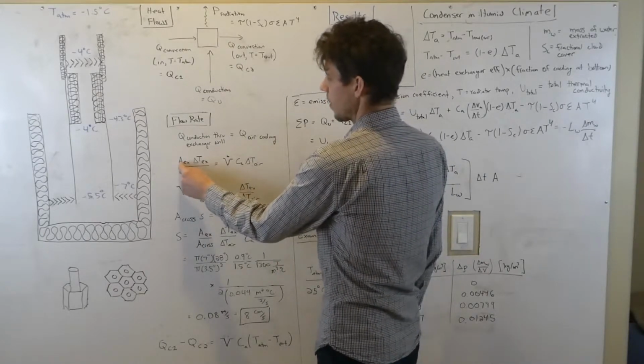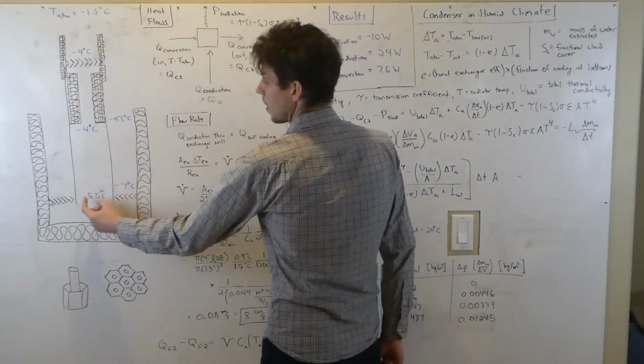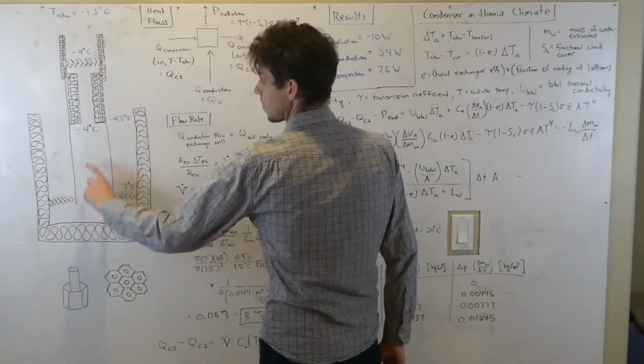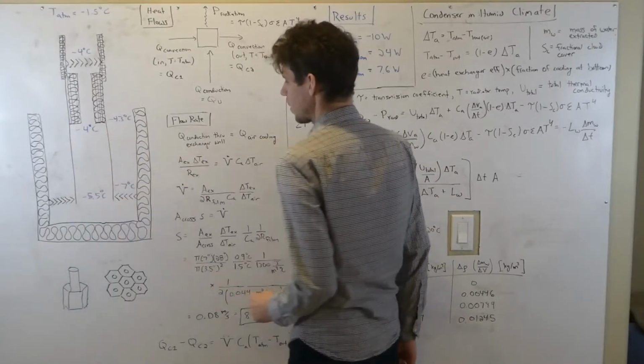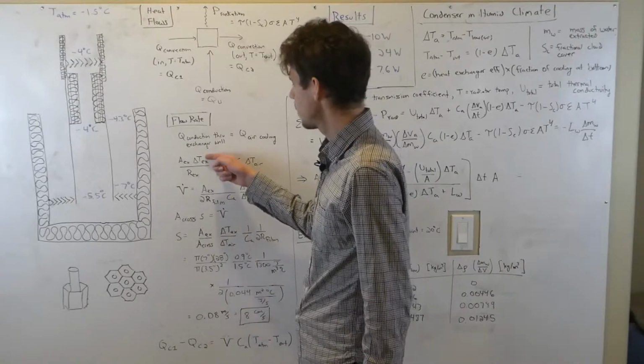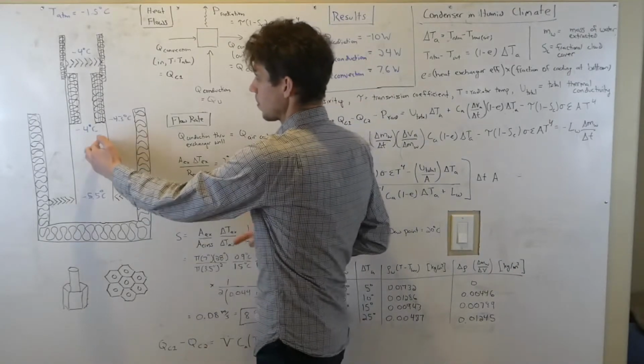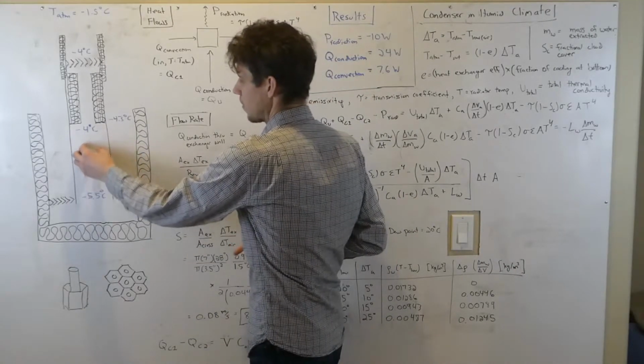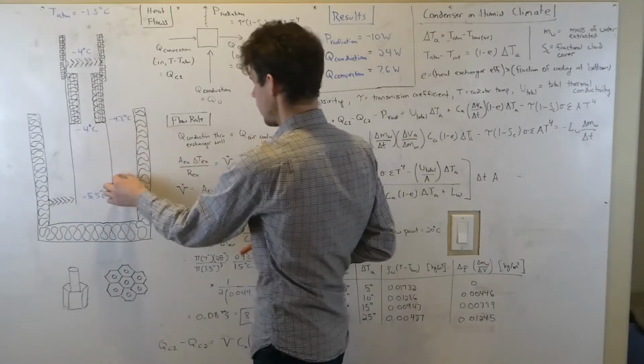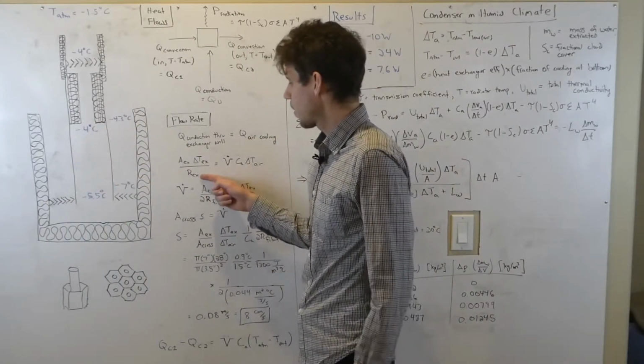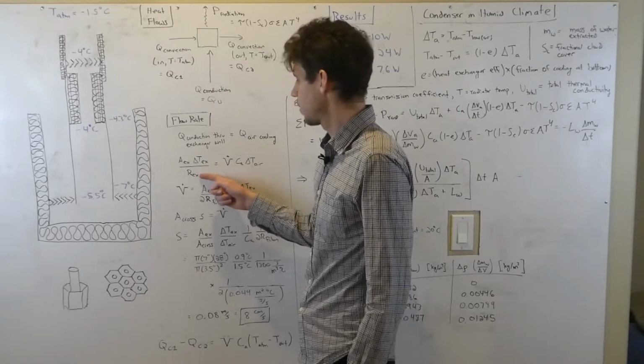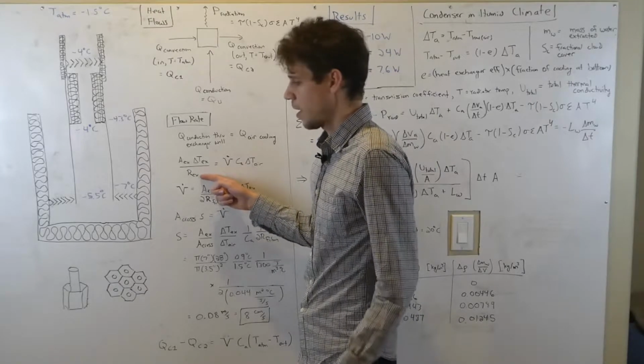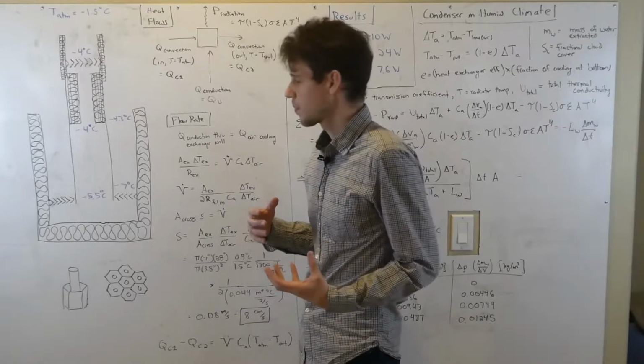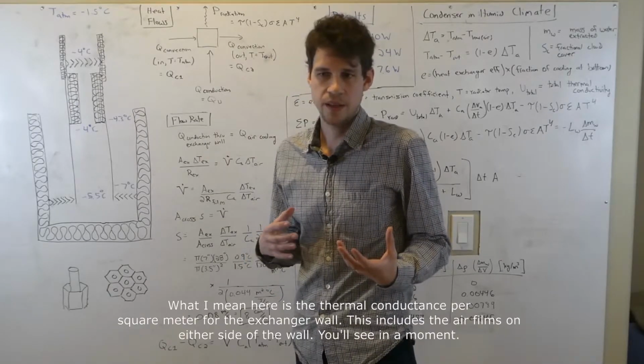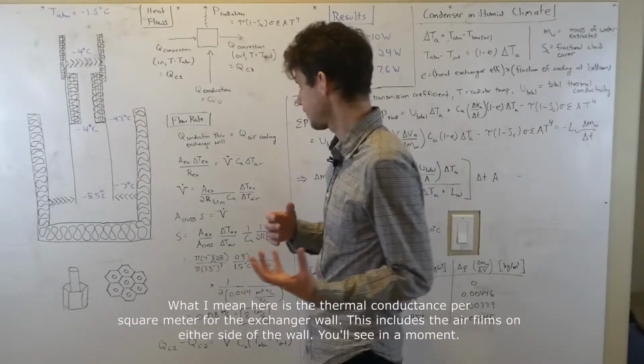So we have the area of the heat exchanger, which would just be pi times the diameter of this pipe times the height. The area of that heat exchanger times the average difference in temperature between this airstream and this airstream, divided by R exchanger. R exchanger is the R value of the heat exchanger, like the reciprocal of the thermal conductivity.